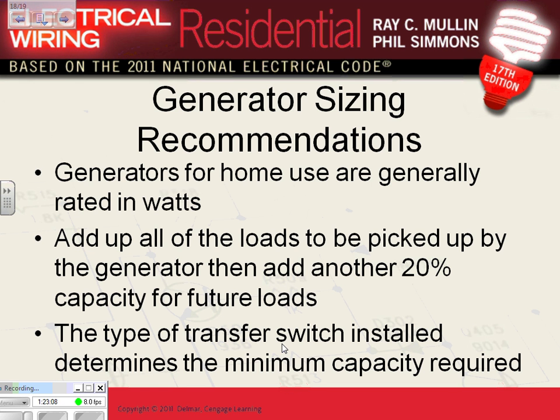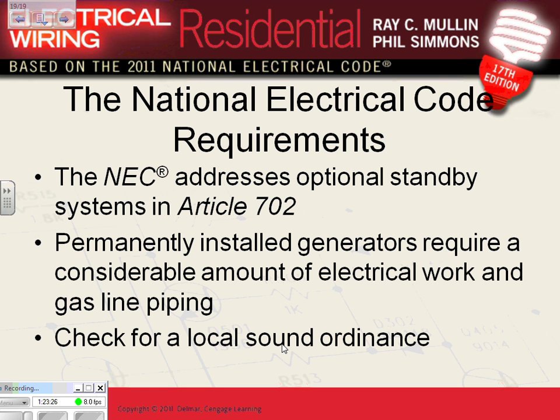When you add your loads, they recommend a 20% increase on the load for future expansion. This is opinion. You can add 25, 20, 10, the same size. It's a good idea to add them though. Okay, address standby system. Generators require a considerable amount of work. Okay, a couple of things, guys. Generators that we don't even think about.